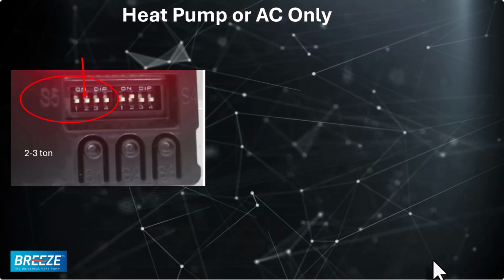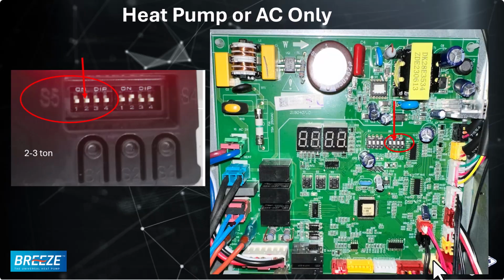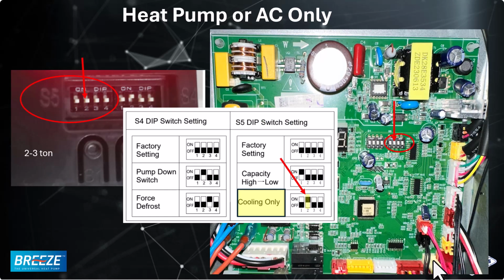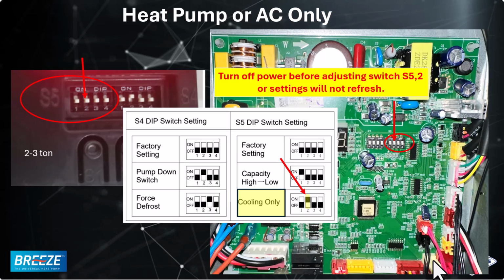If you want to take the heat pump to an AC only unit, we're going to be looking at dip switch bank 5, switch 2. We'll turn this switch to the on position. The power also needs to be off before adjusting the switch.